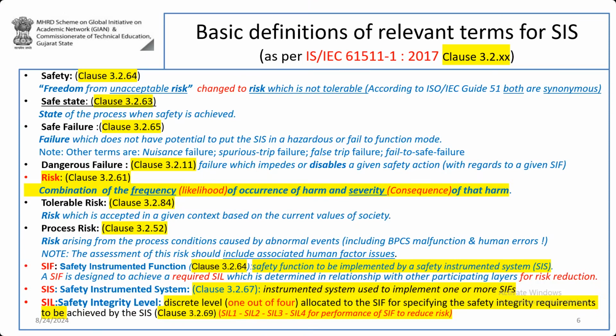Every SIF has a SIL, but every SIL need not be a SIF. I explain why. A transmitter which is capable of SIL 3 is not a SIF. It is capable of giving you performance of SIL 3 level, but it is not a SIF. So SIF has got SIL, but SIL does not give SIF. SIL can be for a transmitter, for a control valve, for a logic solver or PLC. Safety PLC has a SIL rating, SIL rated 2, SIL rated 3, etc. General purpose PLC does not have any SIL rating. So for safety application, you have to deploy a safety PLC and not a general purpose PLC or the general logic solver of BPCS. That's all.